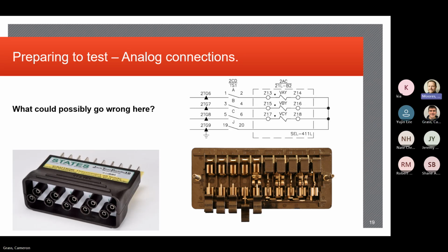Let's dig into this just a little bit further, Kim, just so that we're clear. If you look at the test switch, the way it shows in the schematic, that AC schematic, you've got test 2CD, TS1, and the blades are A, B, C, and J. A, B, C, that's the first three blades on that test switch below. J is the far right blade. And if you look at the physical test knife blades, test switches, whatever, for each of that, they open with the hinge down. So you see that hinge is down, which equates to that little hinge up on the schematic. And that would be terminals 2, 4, 6, and 20, which is correct because the bottom terminals on that FT are the evens and the top terminals are the odd numbers. So it goes 1, 2, top, bottom, 3, 4, top, bottom, all the way to the right.